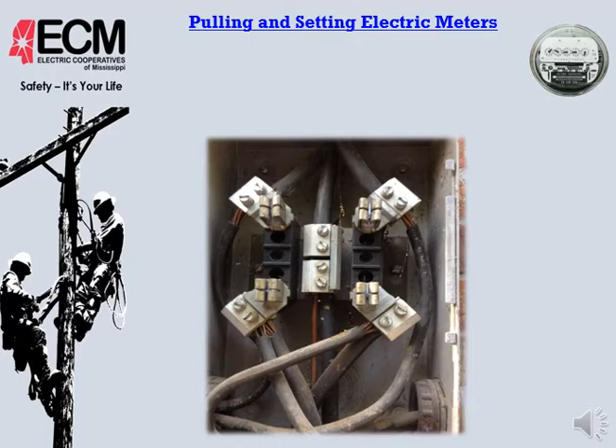All right, so this one here, if you'll notice, on the top side of the meter base they've got some copper coming off the top lugs and going into another coupling there, out into some more conduit or maybe into another building. They're bypassing, getting electricity from the source side of the meter base, and it's not actually being metered.